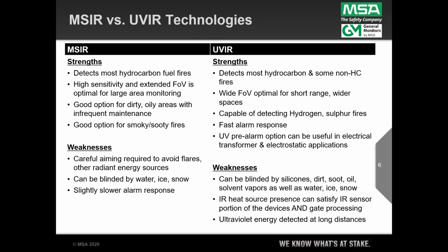Now moving to UVIR, here you've got a device that can see the hydrocarbon fires and it can be tuned to, or set up by the manufacturer to, sense hydrogen and sulfur, and even a magnesium fire. So non-hydrocarbon fires, it's got that capability as well. I showed you on the field of view comparison that the wider field of view is optimal for shorter range, wider space coverage. You can actually maybe save the cost of one device in some cases if it's not a long range requirement on the coverage map. The alarm signal processing is a little faster because it's an AND gate.